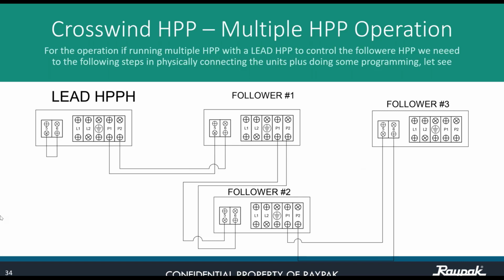Once we have that, the program on the lead heat pump needs to be changed for the operation of the single heat pump to control the follower heat pumps. You need to press and hold the lock pad for 3 seconds. The lock pad is an icon on the display to light up the screen. Then press the fan pad and the plus pad together for 5 seconds, and the code P0, with a value of 0, will be displayed on the LCD display. Press the fan pad to enter the modification code and press the plus pad to change the code to number 1.